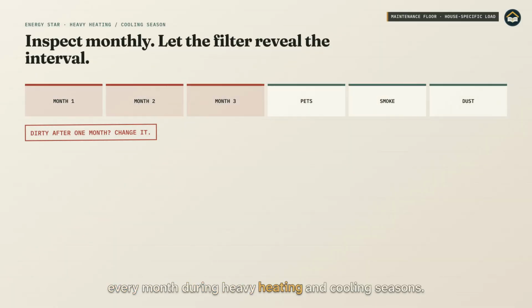Energy Star recommends inspecting the filter every month during heavy heating and cooling seasons. If it looks dirty after a month, change it. At minimum, it advises changing the filter every 3 months, but that is a maintenance floor, not permission to ignore a visibly loaded filter. Begin with a monthly look. Compare the clean filter with what you see later under the same light.